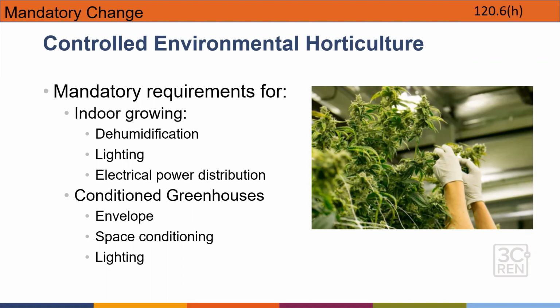Touching on dehumidification, they need to meet federal dehumidifier standards or recover at least 75% of the heat used for reheat. So we want to make sure that we're being as efficient as possible, reusing that heat that we've already generated. And then lastly, conditioned greenhouses need to have at least 2 glazing layers to make sure that we're both keeping the heat out when we don't want it and keeping the heat in when we do want it.